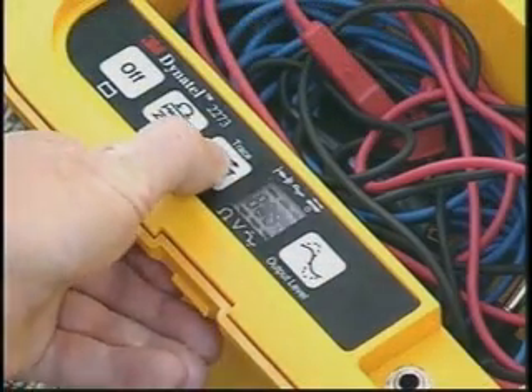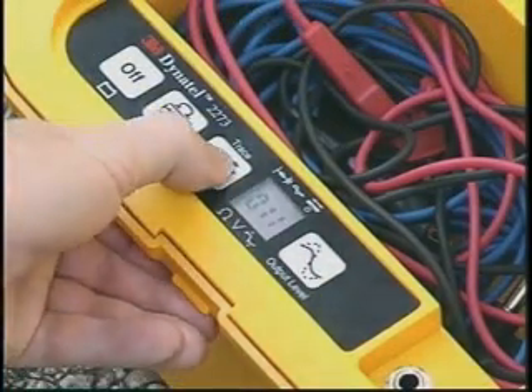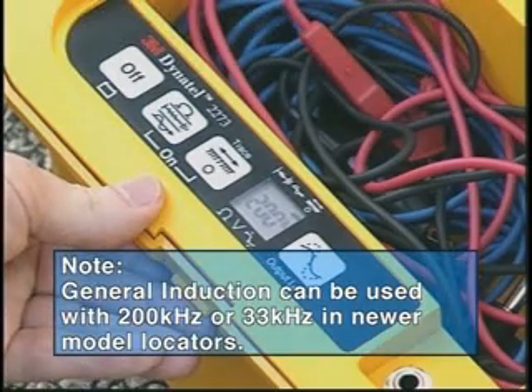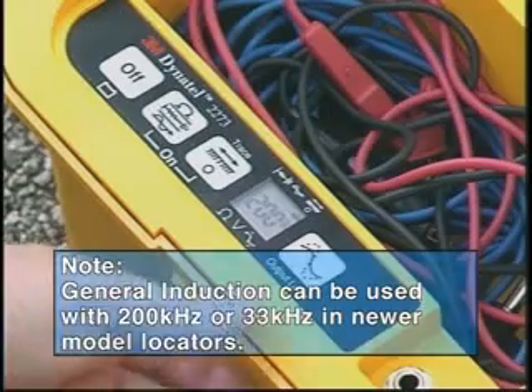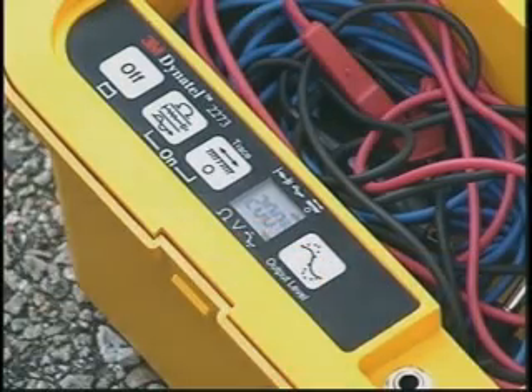Press the trace key to turn the unit on and select the 200 kHz frequency. You can also use high power, so press the output level key to select high output power when the received signal is weak. You should be aware, though, that the induction method applies a signal to every conductor in the immediate area near the transmitter.